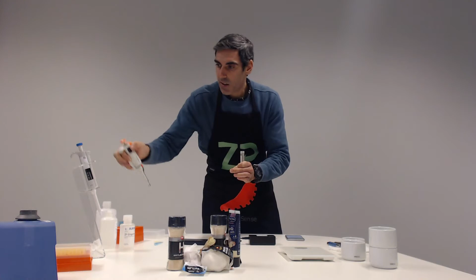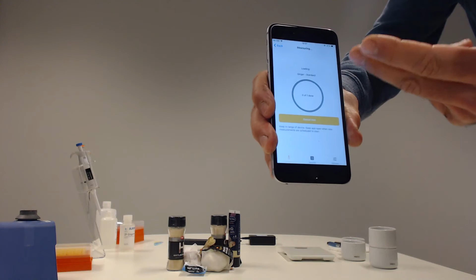And now I'll move a bit closer to the camera again. So now I'm going to just press measure, and so the measurement has begun, and we have to wait for this circle to complete, to be fully yellow. So what's happening here basically is we are running a CV scan, and that CV scan will indicate the oxidation of gingerol, and the peak current will be proportional to the concentration of gingerol in the sample. So one thing that's important, I have mentioned before as well, is to prepare all samples in the same way so that you can compare the samples.